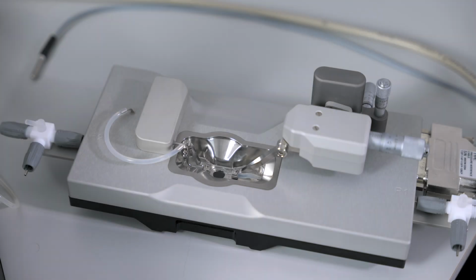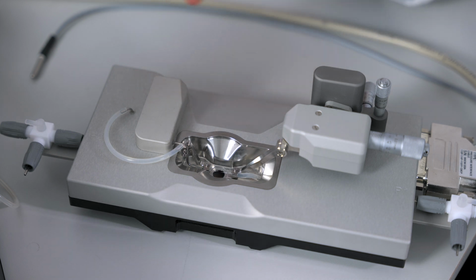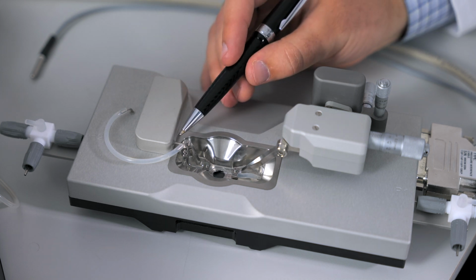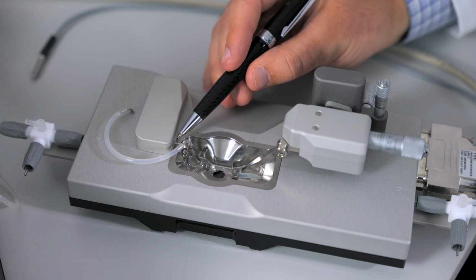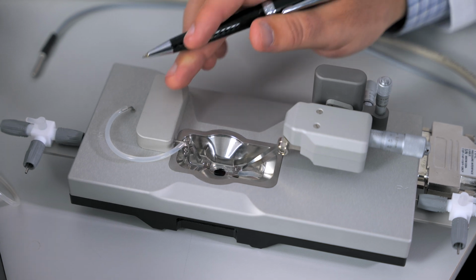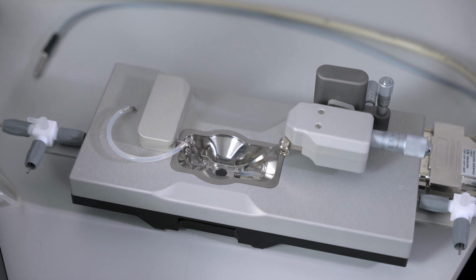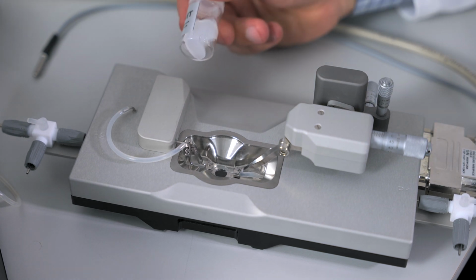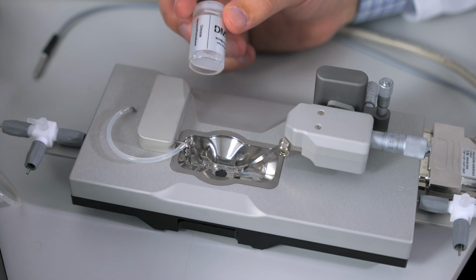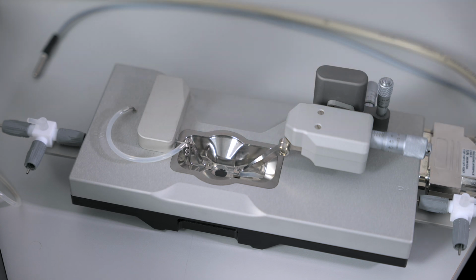If you begin to notice red or brown discolorations in your chamber, there is a thorough cleaning guide in this section of the 114 user guide. In maintaining the force transducer on the chamber, you must always be cautious when handling this cannula mount or the transducer arm itself. After cleaning, make sure that there is clear grease surrounding this transducer arm coming from the housing. If you notice that it has been cleaned away, you can take some of the clear grease that came with your system, use a pipette tip, and apply more grease to that pinhole.